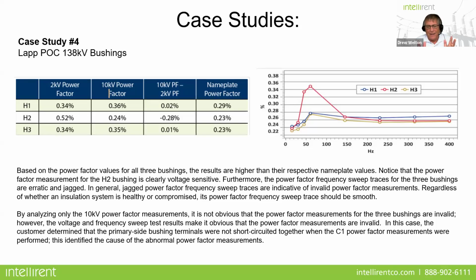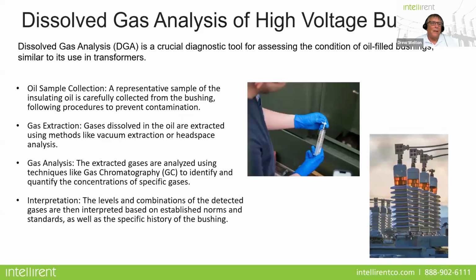In this particular case, the customer determined that the primary side bushings of the terminal were not shorted together when the C1 power factor measurements were performed. So lo and behold, you could have looked at the 60 hertz values and said, "Oh my gosh, H1 and H3 look okay, but H2, that's way out of whack." But in this case, the frequency sweep tells you that you just didn't run the test properly.